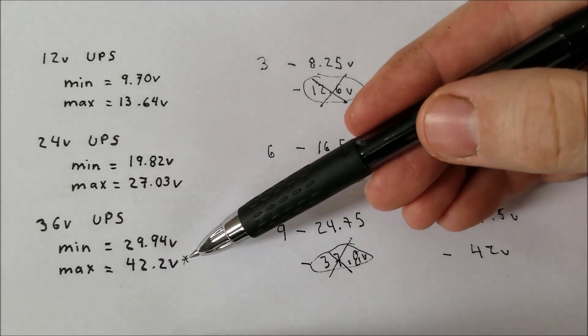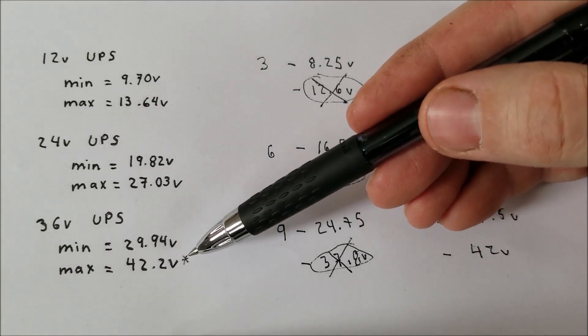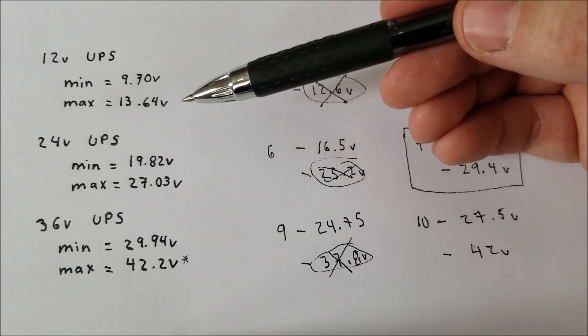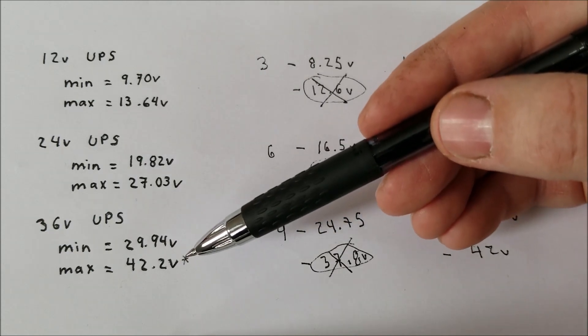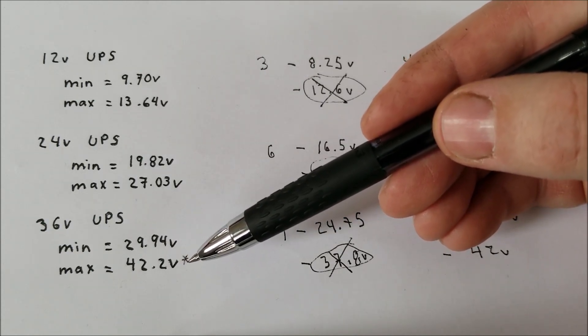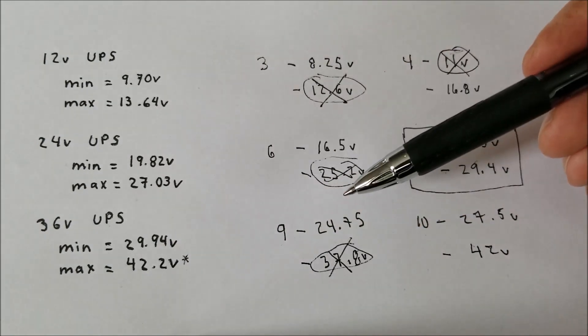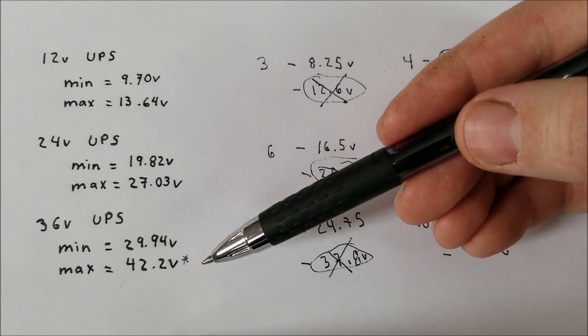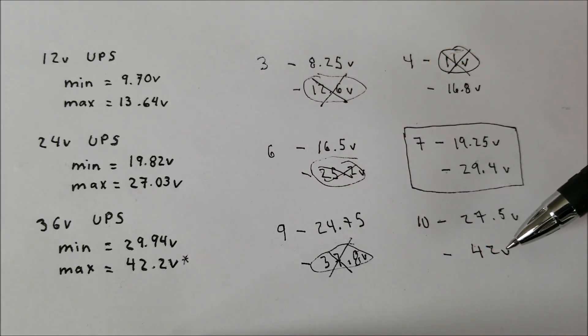Now I did notice I put an asterisk here. The reason is that although these UPSs, when they hit the maximum voltage, pretty much remained at that maximum voltage, this UPS only briefly saw 42.2V, but then went down to roughly 41V. So even though it did go up to 42.2V, which is slightly above 42V, it only did it for a short period of time, and then it would settle.